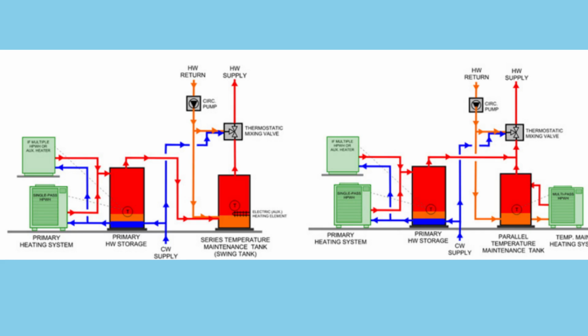The first is the swing tank. Here, an unstratified tank is placed in series with the primary storage tank. During high water use, overheated water from primary storage flows through and passively heats the swing tank. During low use, the swing tank cools, and a backup electric resistance element kicks in. The second is the parallel loop tank. This design uses a separate multi-pass heat pump to reheat the recirculation loop. It allows primary storage to run at lower temperatures for higher efficiency, but it requires more heat pump capacity and cost. Parallel loop systems are often used when recirculation losses are high, but hot water usage is relatively low.